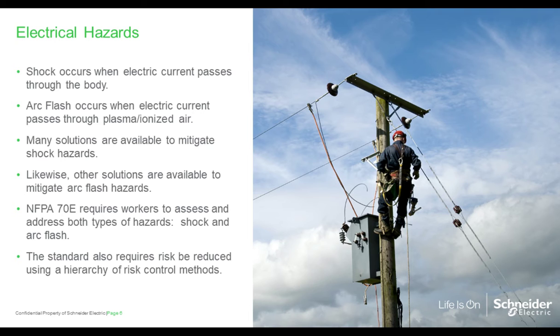So, our recognition of arc flash hazards is much newer. The concept of arc flash didn't even appear in safety standards like 70E until 1995. So there's another related hazard called arc blast, and that's the explosive effect that results during an arc flash event. And it's caused by the rapid expansion of superheated air and other materials. Arc blast appears to be a function of containment and fault current and some other factors, but it's a secondary hazard, and it's the result of the primary hazard, which is arc flash. So, it's critical that qualified workers be able to identify the hazards and protect themselves from the risks that result from both types of hazards, shock and arc flash.